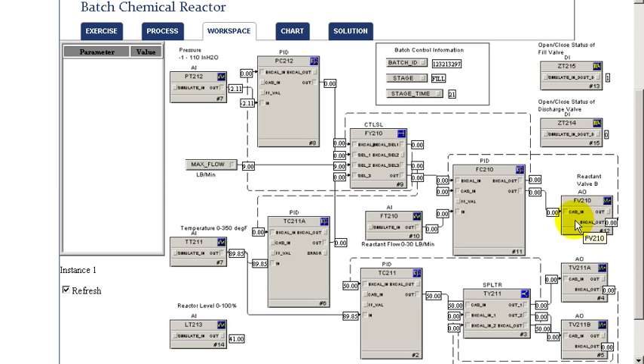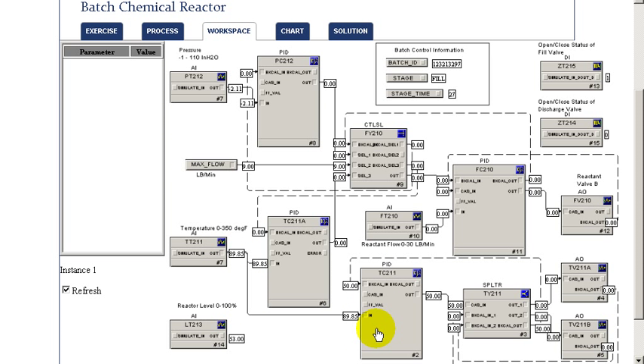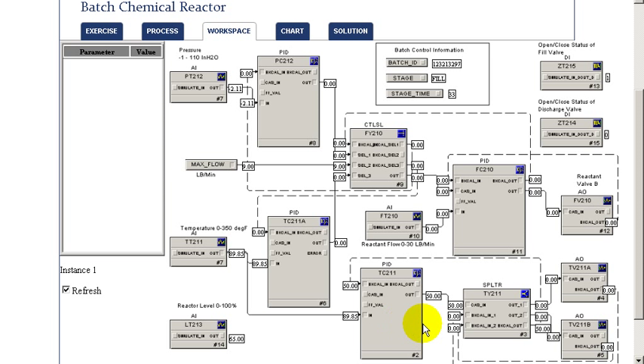So the temperature control of the vessel is done with a PID. Its output is going to a splitter block, and that splitter block is used then to adjust either a cooling or heating valve to the unit.